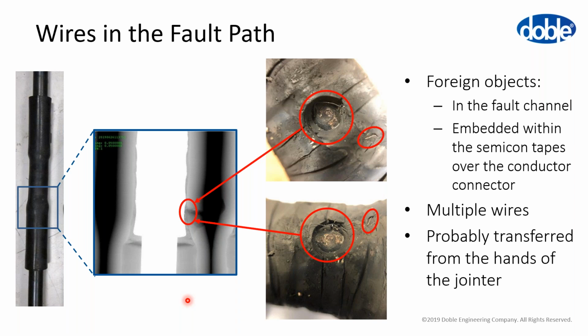We could sample those wires, and I'm going to show you the electron microscopy in a minute. If there were multiple, I can only assume that they got stuck into those tapes when the jointer was lapping those tapes on. Either he didn't change his gloves, he didn't wash his hands, but they've ended up in there somehow.